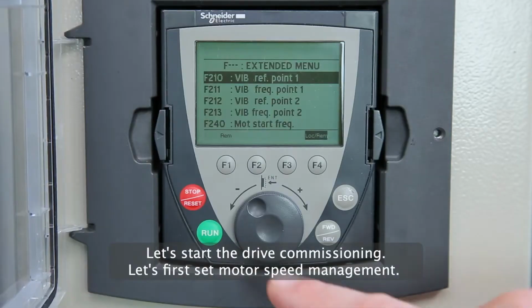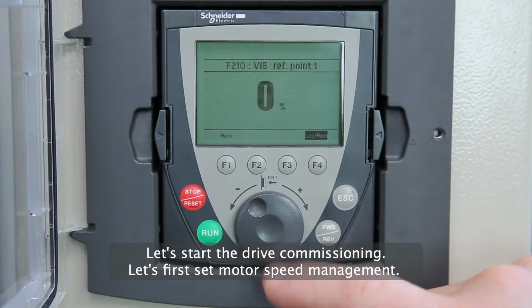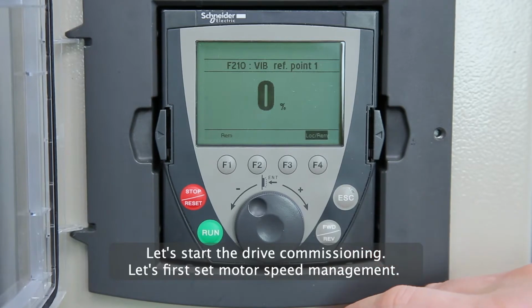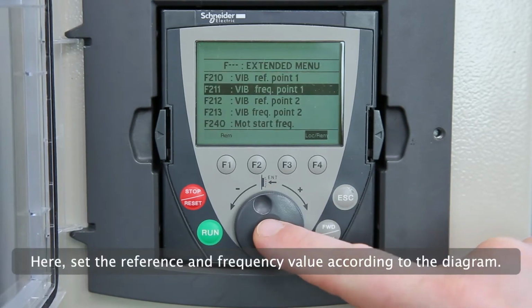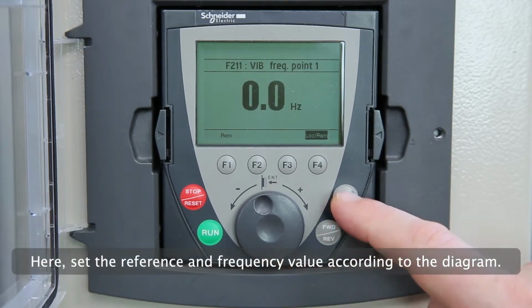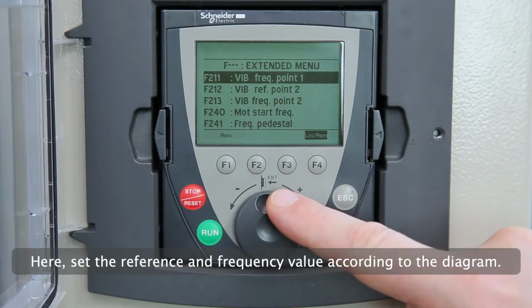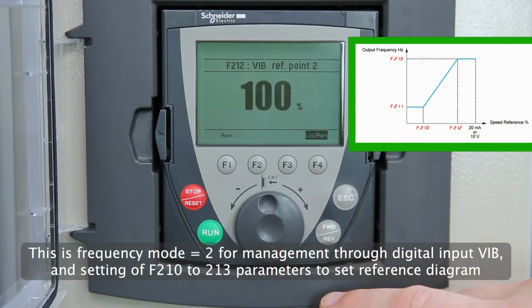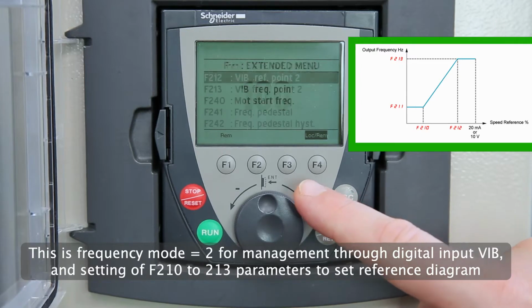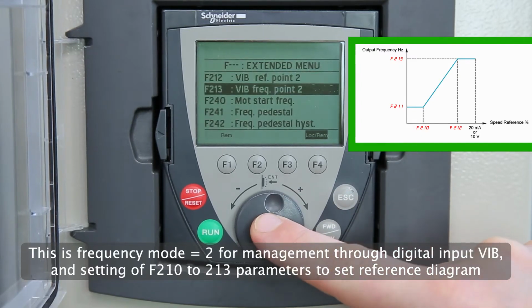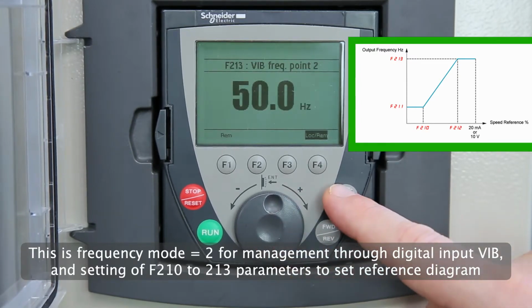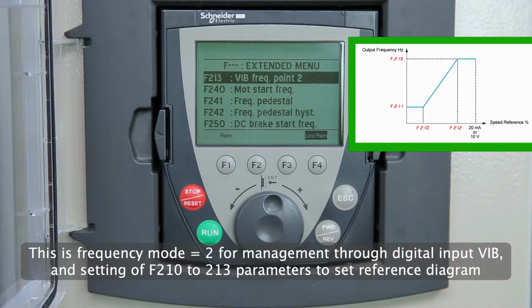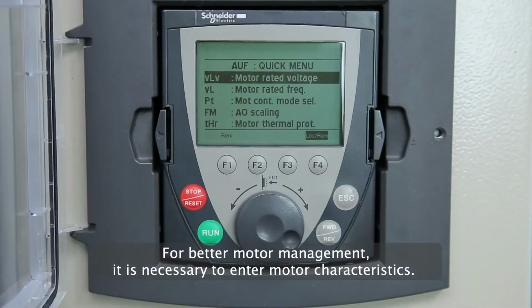Let's start the drive commissioning. Let's first set motor speed management. Here, set the reference and frequency value according to the diagram. This is frequency mode equals 2 for management through analog input VIB and setting of F210 to F213 parameters to set the reference diagram. For better motor management, it is necessary to enter motor characteristics.